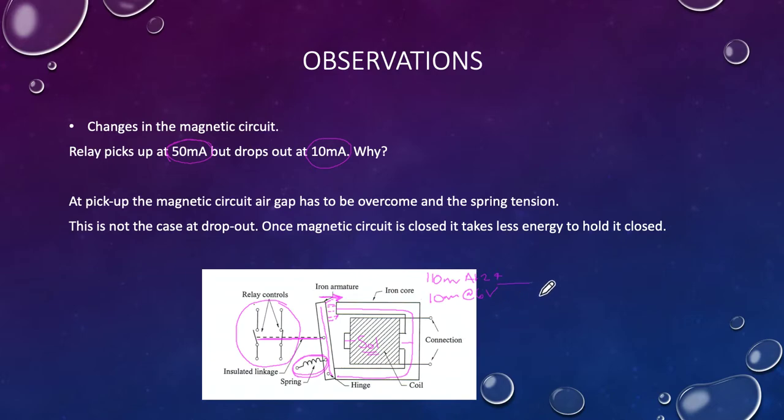We dropped it down to the dropout point at 6 volts and got 10 milliamps. Somewhere in the middle was the pickup point at 50 milliamps. We were able to drop much lower than 50, only took 10 before there was insufficient magnetic field to hold it in and the spring would then pull the thing open. So changes in the magnetic circuit: the relay picks up at 50 milliamps but drops out at 10. At pickup, the magnetic circuit has an air gap and spring to overcome, but at dropout it doesn't have to overcome those things and drops out much earlier at 10 milliamps.